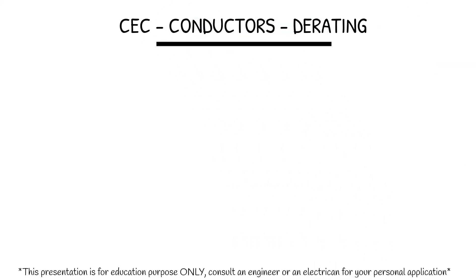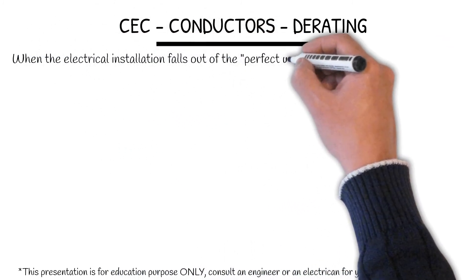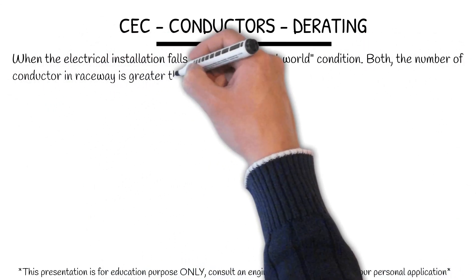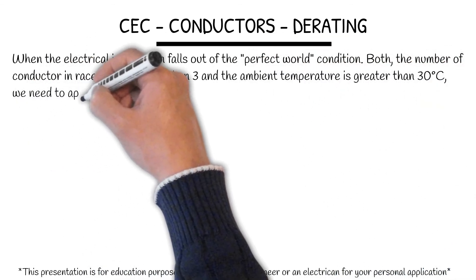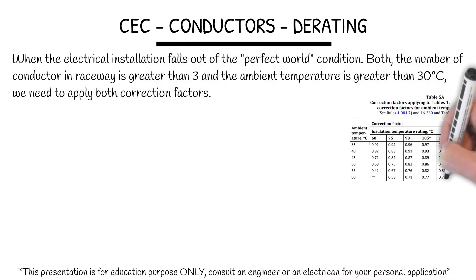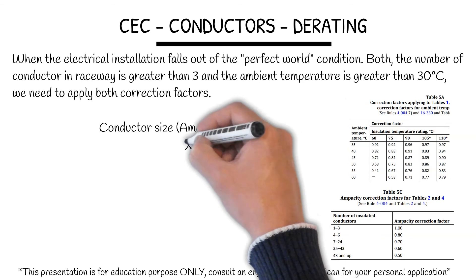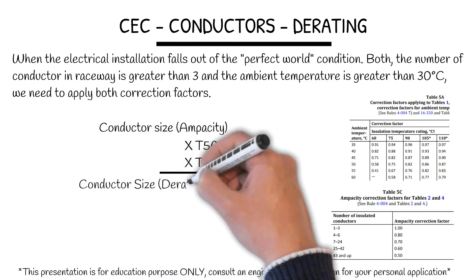When the electrical installation falls out of perfect world conditions — both the number of conductors in the raceway is greater than 3 and the ambient temperature is greater than 30 degrees Celsius — we need to apply both correction factors from Table 5A as well as Table 5C. We get the conductor size and ampacity, multiply by both correction factors, and compare the new derated ampacity to see if it's still carrying the load safely.